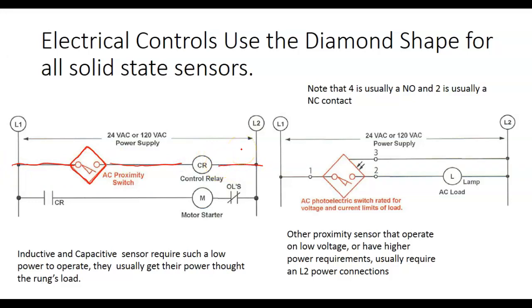In motor controls, you'll use an inductive sensor that's solid state. It only has 2 wires, but these lines are 120 volts. To generate enough power to operate the sensor, it drops about 4 volts, but that still leaves you 116 volts to run the load. So they're actually powering through the load - these 2-wire solid state sensors.